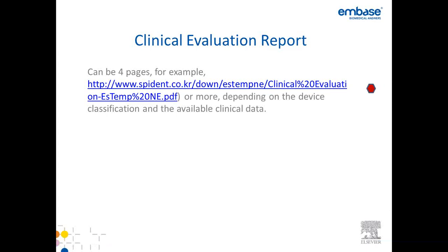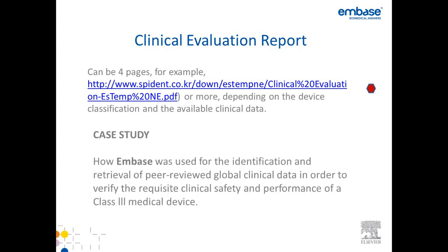Very good. Okay, so I will be giving you an example of a clinical evaluation report that was submitted and accepted by the regulatory body that it was submitted to. This particular case study was for a Class 3 medical device, and the intent was to do a global review of the clinical data to verify the clinical safety and performance of this device.